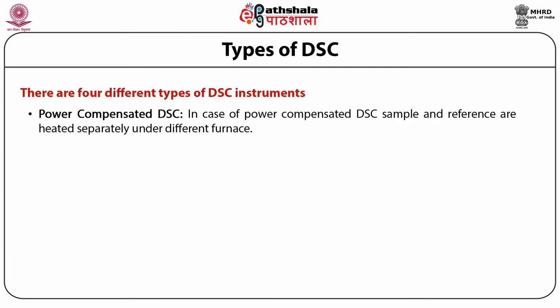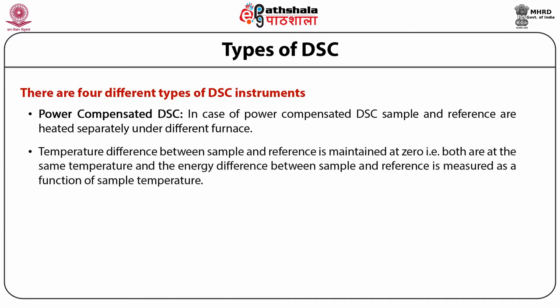Types of DSC: There are four different types of DSC instruments. The first one is power compensated DSC. In case of power compensated DSC, both reference and sample are heated separately under different furnaces. The difference of temperature between reference and sample is maintained at zero — that is, both are at the same temperature. The difference of energy between reference and sample is recorded as a function of sample temperature. Two independent heating units are employed for power compensation DSC.